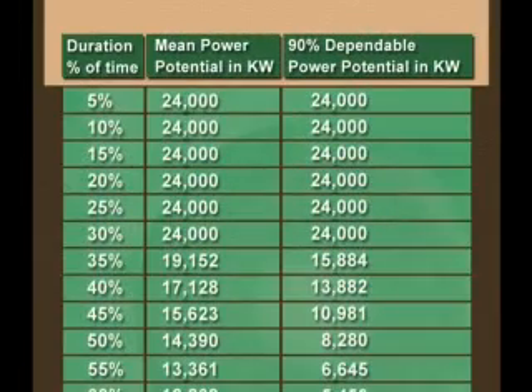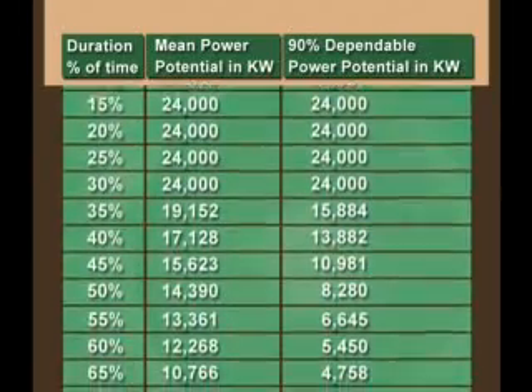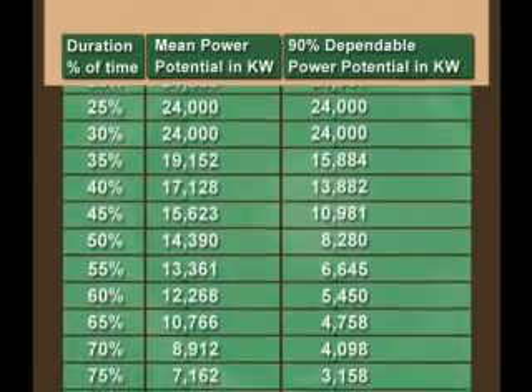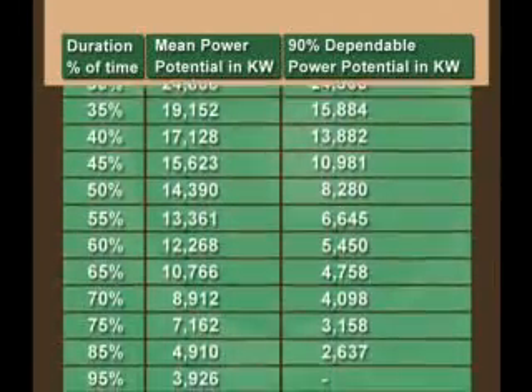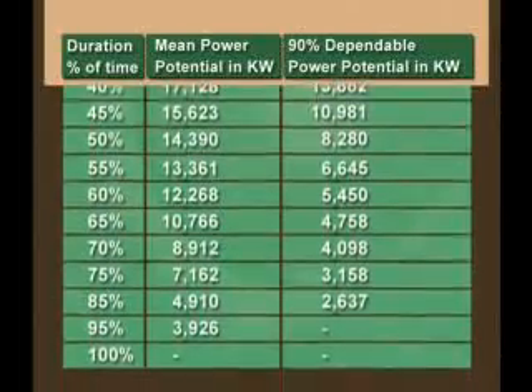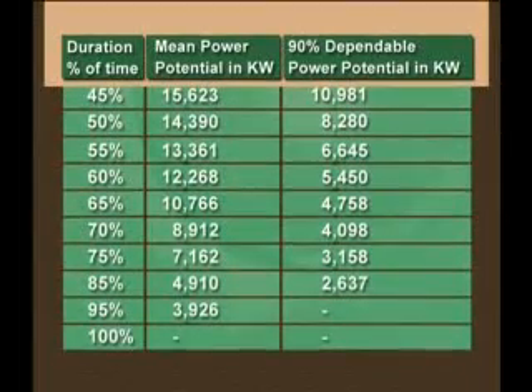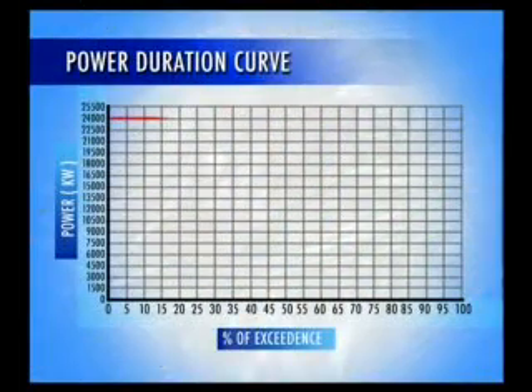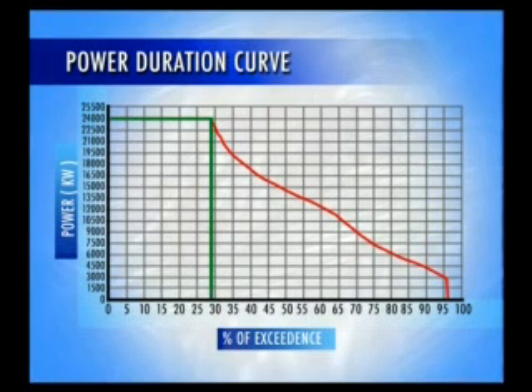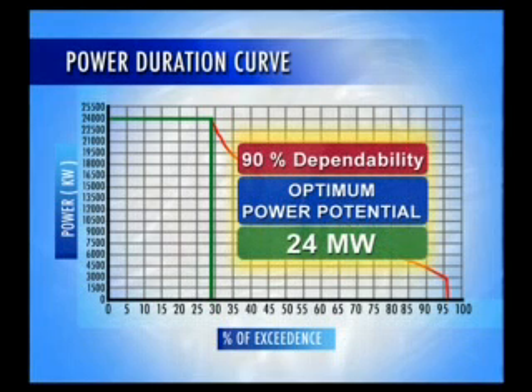The power studies are carried out for the entire observation period considering 90% dependable year and are tabulated. Based on the values in the table, power duration curve is drawn. As seen from the curve, about 24 megawatts is available for about 29% of the time in a year with 90% dependability. Hence, 24 megawatts is taken as optimum power potential of the scheme.